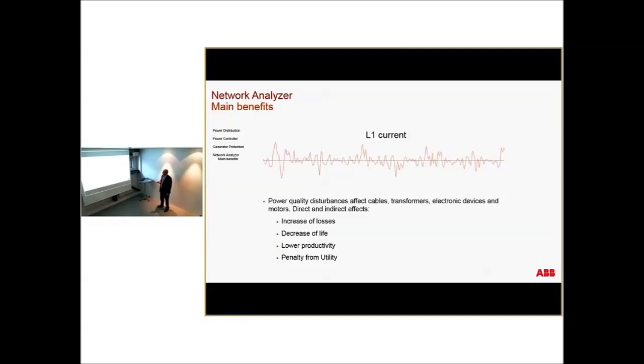That's another important point. It was available in the Emax 1, but now, again, the power of the device is much higher. We have increased the capacity of the network analyzer. This is becoming more and more important because poor quality electrical power creates big problems. It increases losses, decreases the life of the devices inside the circuit, decreases productivity, and in some cases you also get penalties from utilities.